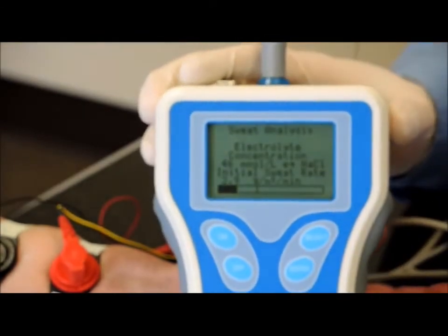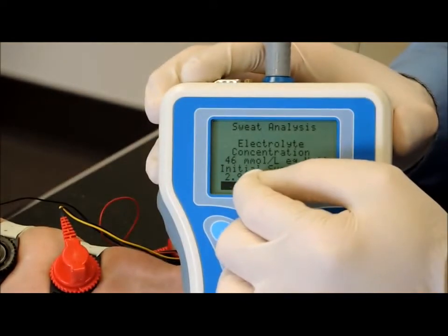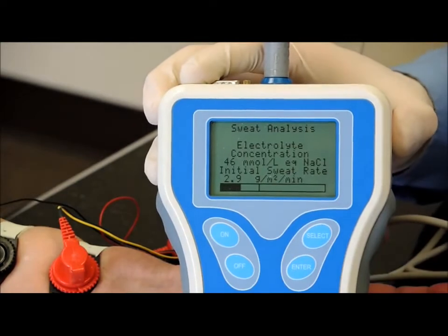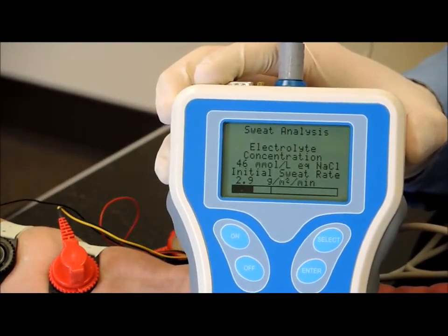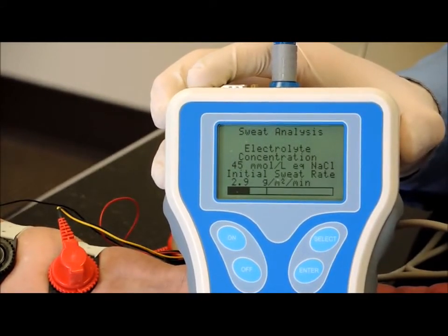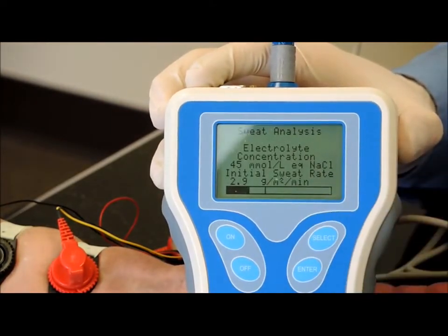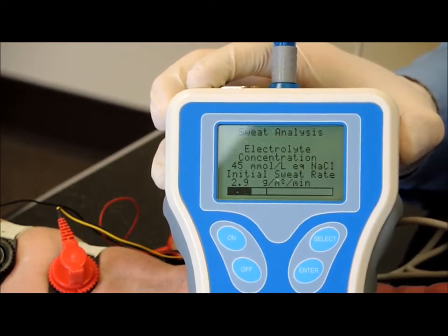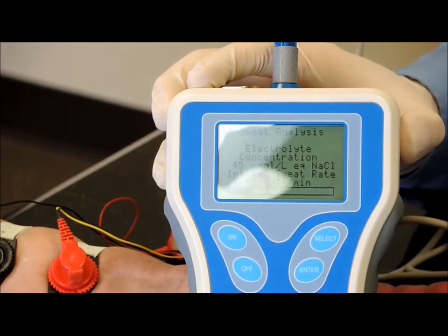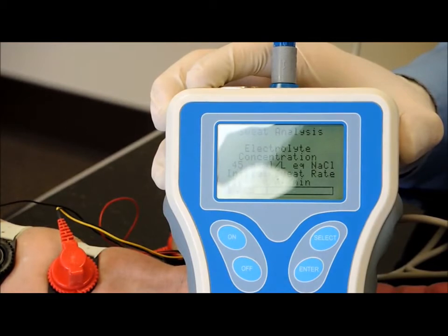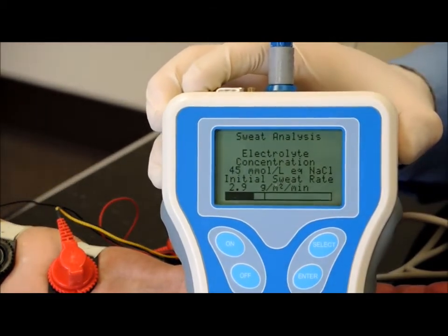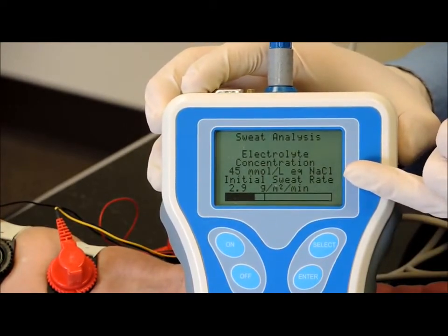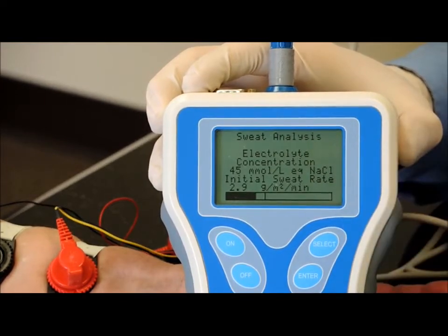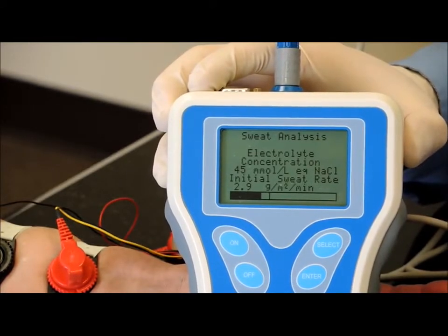You also see at the bottom of the screen a progress bar. That progress bar is set for 8 minutes. You'll also see near the first part there's a little line. The first 3 minutes of the progress bar is where we measure the readings, but we don't take that into account for the final reading. The final reading is based on the final 5 minutes of collection, and it's an average of those readings over the 5-minute period. So keep that in mind. We don't average in the higher values typically seen with the first sweat that comes from the patient. We only average the values over the final 5 minutes. Also keep in mind, if you had chosen to suppress the reading, you would not see that conductivity value nor the sweating rate. You'd only be seeing the progress bar at this point. And so those are some differences if you had chosen to suppress the reading.